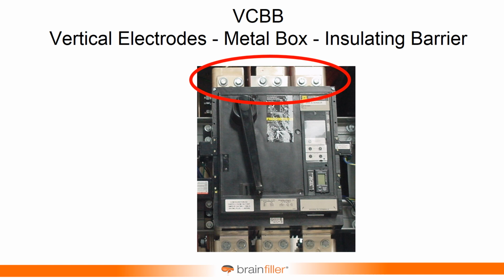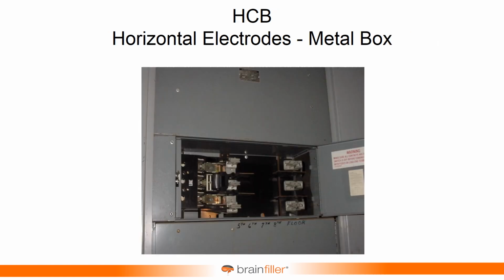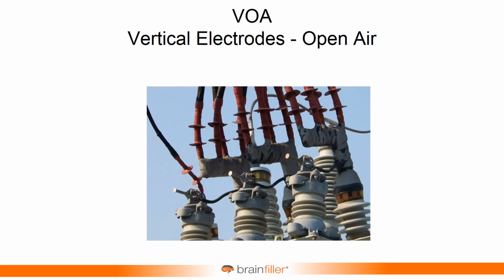And then we have the HCB, the horizontal. And this might be like where you have stabs or something like that. If an arc flash were to occur, as you see here on these stabs where the fuses go, the fuse mounts, it may tend to behave more like horizontal electrodes coming out at a person. And then we have the vertical electrodes in open air. That's just a basic arc flash in open air, again, similar to what we had in 2002.